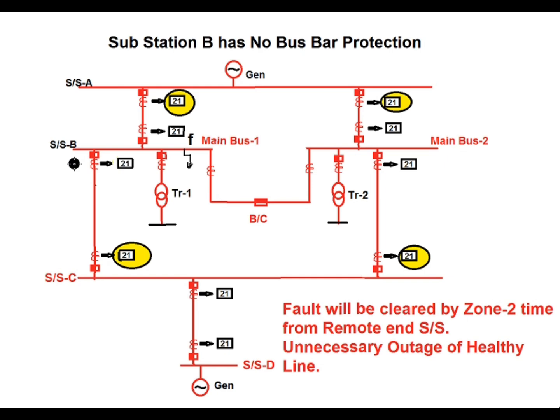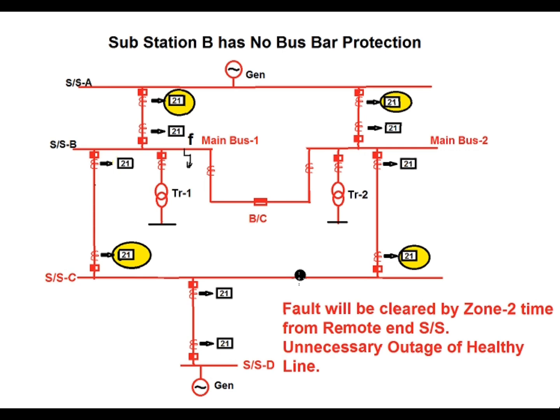In this figure, substation B has two main buses — main bus 1 and main bus 2 — connected via a bus coupler breaker. Substation B is connected to substation A via one double circuit line, where one circuit is connected to main bus 1 and another circuit is connected to main bus 2. Substation B and substation C are also connected via one double circuit line, similarly split across main bus 1 and main bus 2. Substation C to substation D has one single circuit line, and substation D and substation A are each connected by a source.